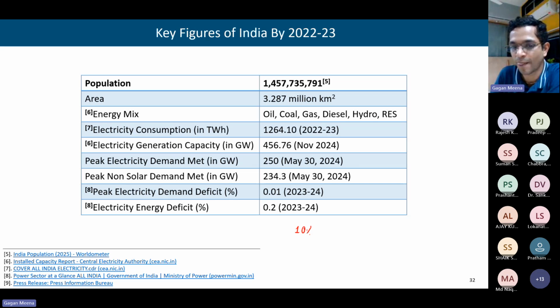10% of the availability of these conventional generators—90% of the time their availability is around 90%. 10% of the time they will be on maintenance or some failure; some scheduled, planned, or unplanned forced outages are there. Forced outage rate is around 10%. Then scheduled maintenance is also there. If we combine both, the availability factor is less than 90%.